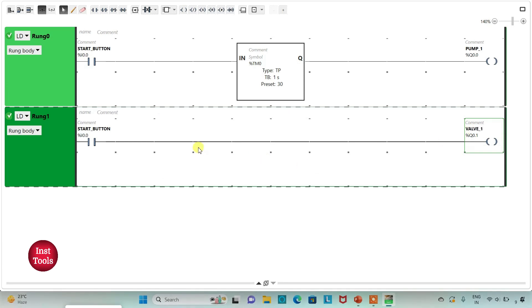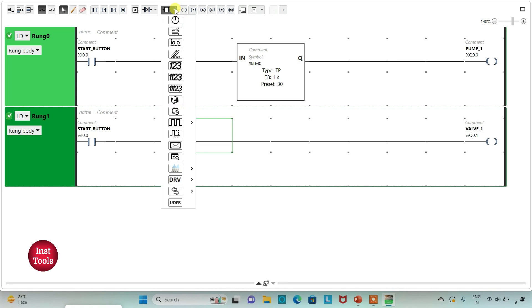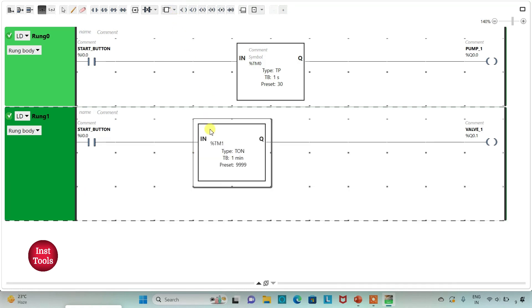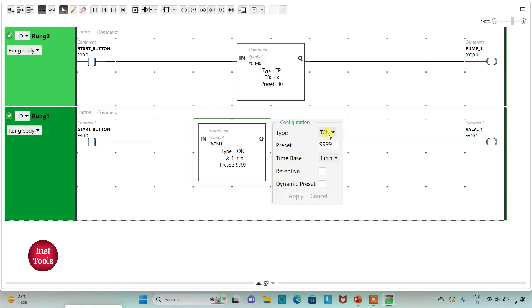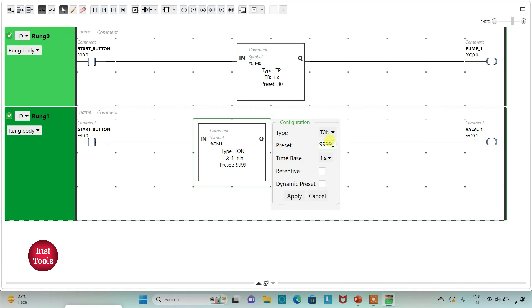When the start button is pressed, Pump 1 will be on, but Valve 1 should turn on only after Pump 1 gets turned off — that is after 30 seconds. So for this I will use an on-delay timer for Valve 1. I will insert a TON timer, change the time base to 1 second and preset value to 30, then click Apply.